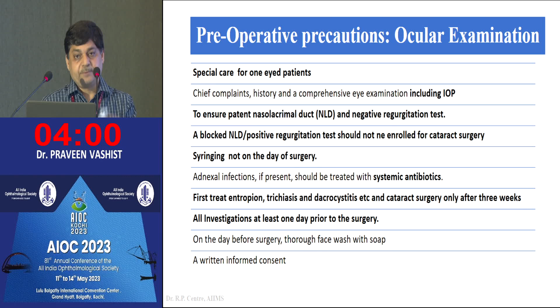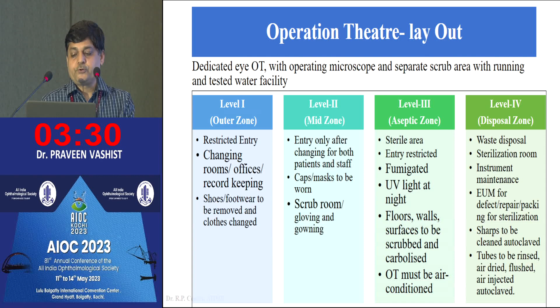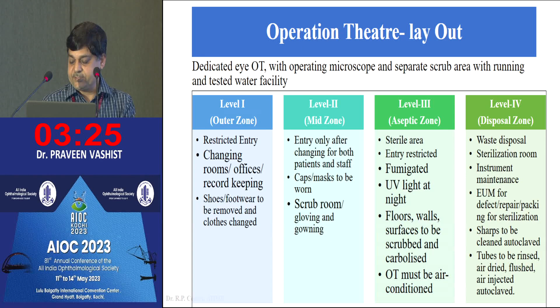As she has mentioned, there are four zones for operation theaters, and each level has to be taken care of. In fact, level 3, the aseptic zone, is the most important one. It should be totally sterile. It should be fumigated. UV light is suggested at night. Floor and wall surfaces to be scrubbed and carbolized, and the OT must be air conditioned. So these are specific for level 3 aseptic zones.